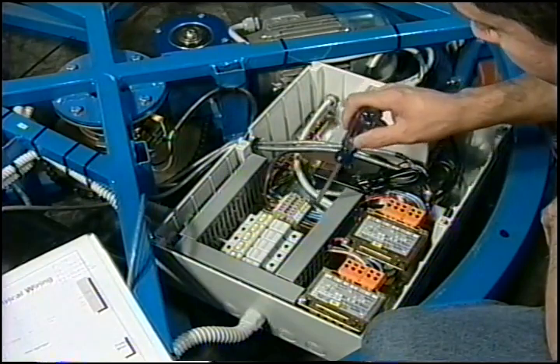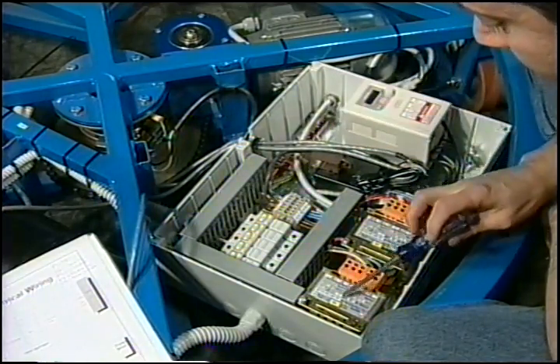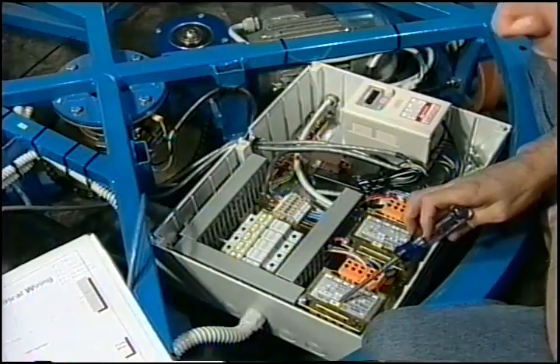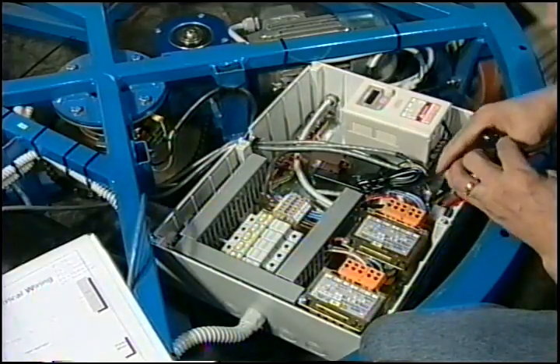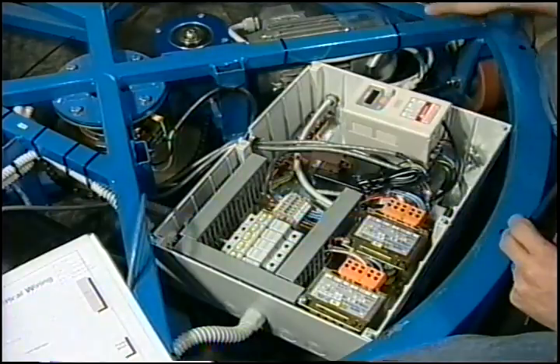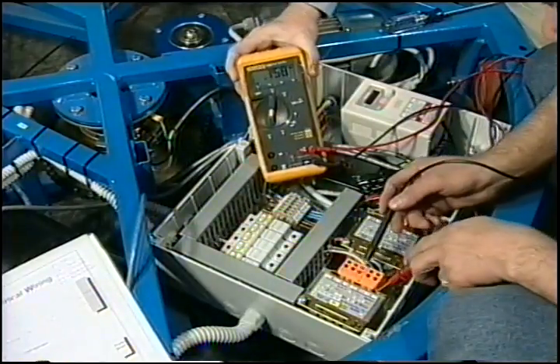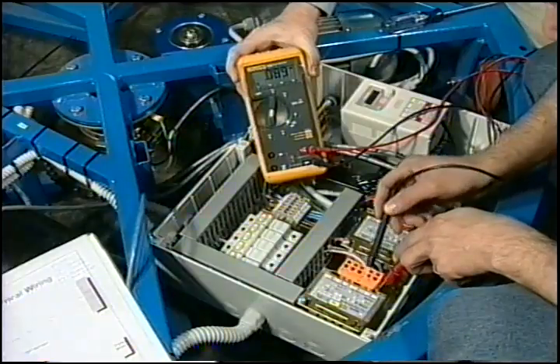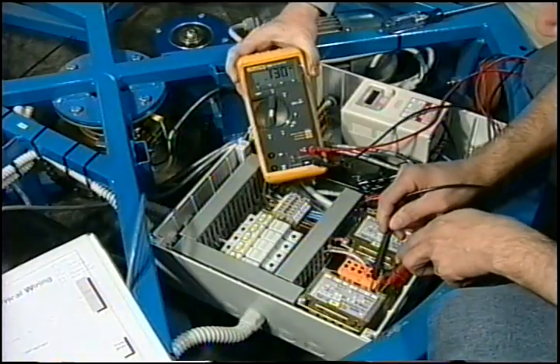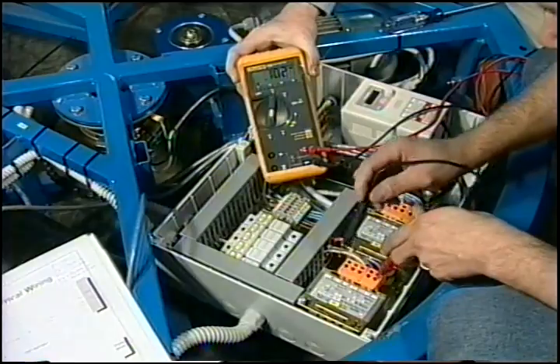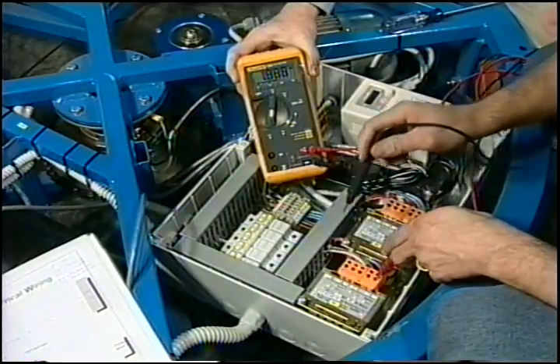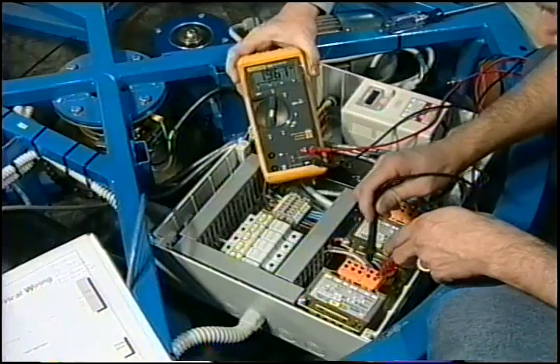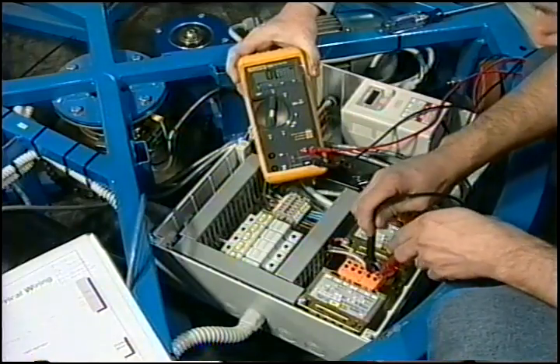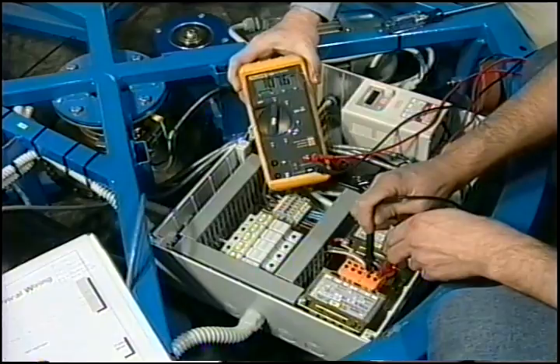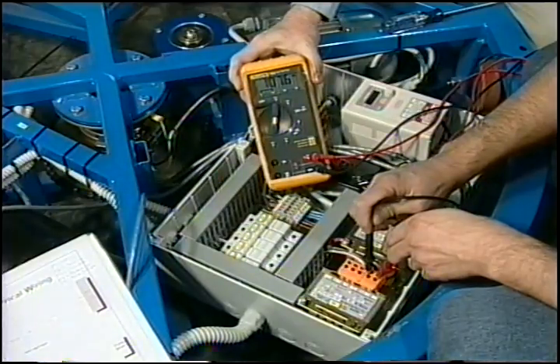After it comes out of here, it first sends power to your TR1 transformer, which is always live at 120. If you wanted to check your TR1 transformer, the first two terminals on your left here is your main power, your primary of the transformer. Your first terminal, which is labeled 0, is your neutral. Your hot lead is your 110 terminal here. So if we were to take our meter and measure across that, we would read 110, or close to that.